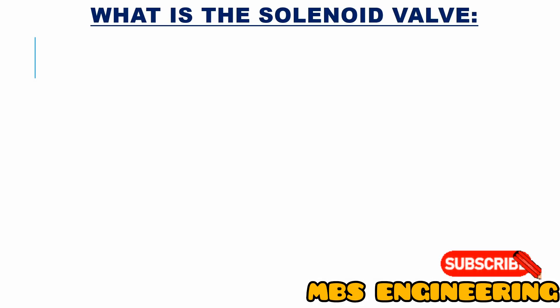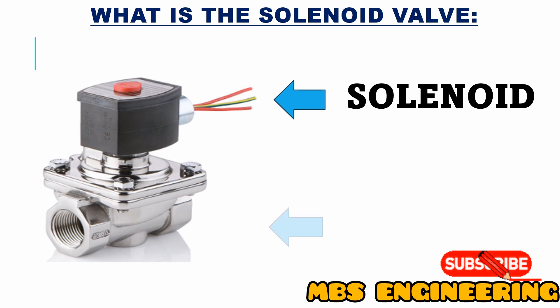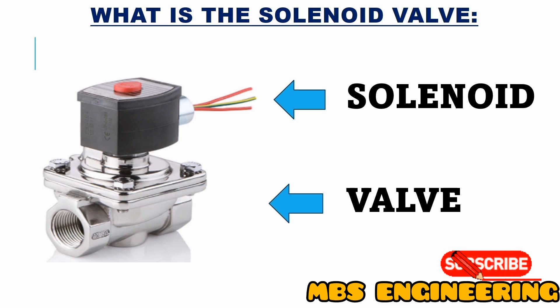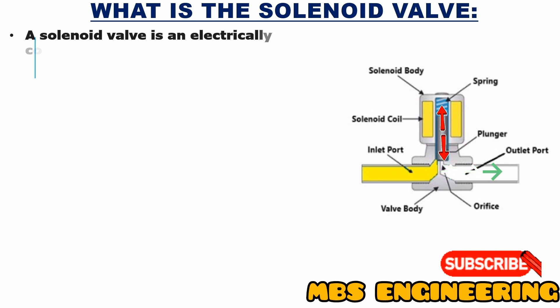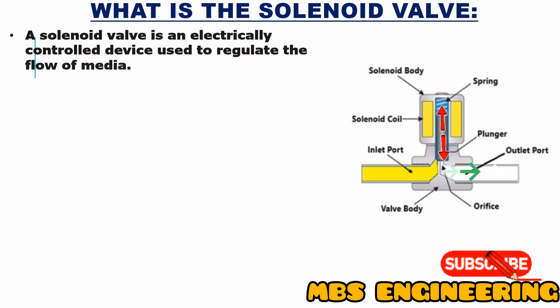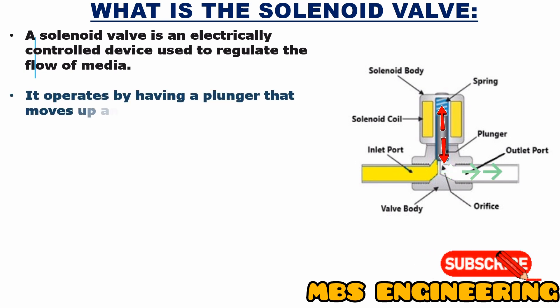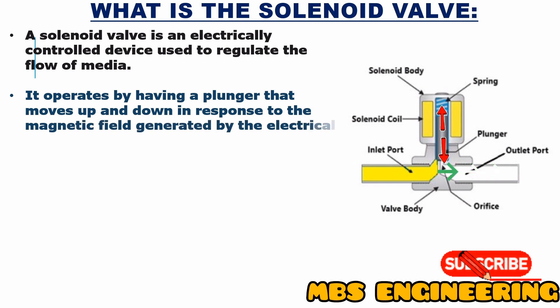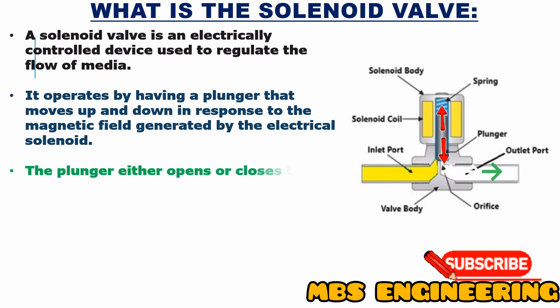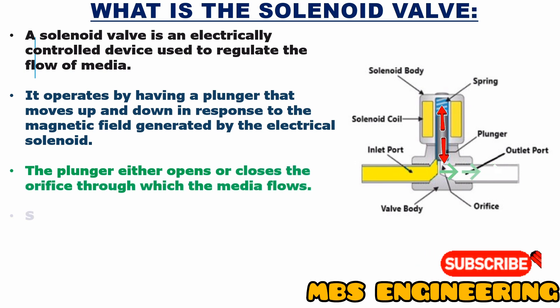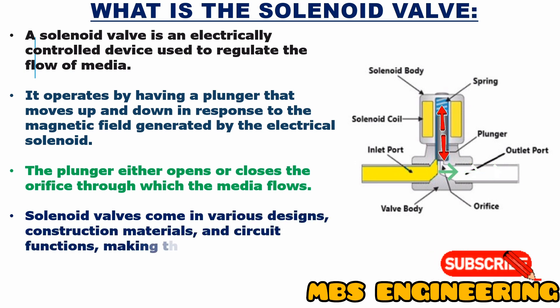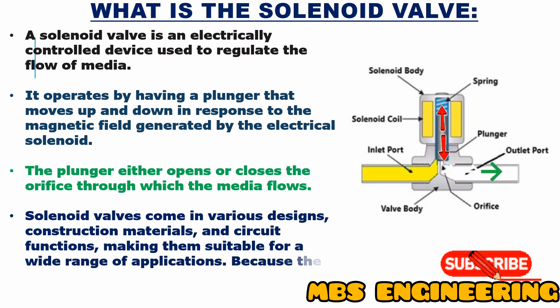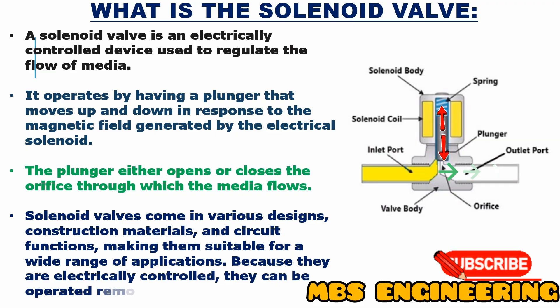Please refer to the picture. The top part is called the solenoid, and the bottom part is called the valve. A solenoid valve is an electrically controlled device used to regulate the flow of media. It operates by having a plunger that moves up and down in response to the magnetic field generated by the electrical solenoid. The plunger either opens or closes the orifice through which the media flows. Solenoid valves come in various designs, construction materials, and circuit functions, making them suitable for a wide range of applications. Because they are electrically controlled, they can be operated remotely and automatically.